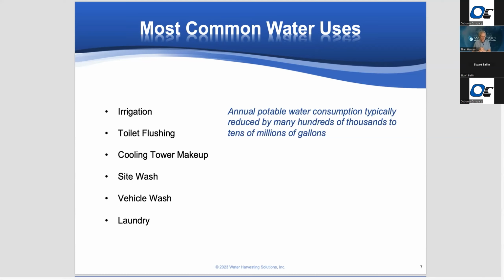Toilet flushing is practical only if you're doing a new construction project, because you have to run different types of piping to be able to do that. So on a retrofit, maybe, but for an existing building, probably not, toilet flushing is not going to be an option. Cooling tower makeup is probably our number one biggest reuse. Cooling towers use literally tons of water a day, and we have many applications where we're collecting water for cooling tower makeup, and we treat the water, soften it as necessary, filter it so that it makes very high quality water for use with the cooling towers.